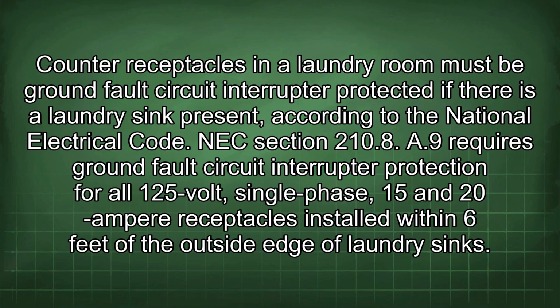Counter receptacles in a laundry room must be ground fault circuit interrupter protected if there is a laundry sink present, according to the National Electrical Code. NEC Section 210.8(A)(9) requires ground fault circuit interrupter protection for all 125-volt, single-phase, 15 and 20 ampere receptacles installed within 6 feet of the outside edge of laundry sinks.